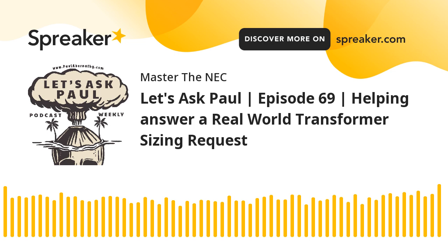All right, let's get back to our list here. So those secondary conductors, first thing that we automatically know, me and you, we know this. They obviously can't be less than the 78 amps because that's the load. But also, since our secondary transformer puts out a potential to handle 83 amps, so we already know it can't be less than the 83 amps, right? Okay. Now, I shouldn't say that.